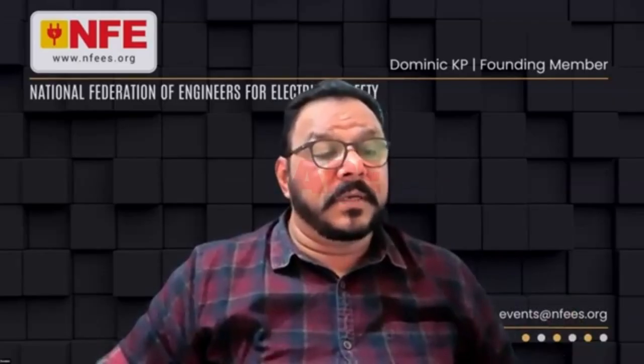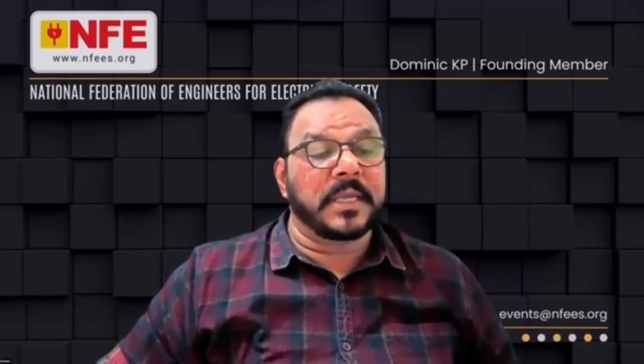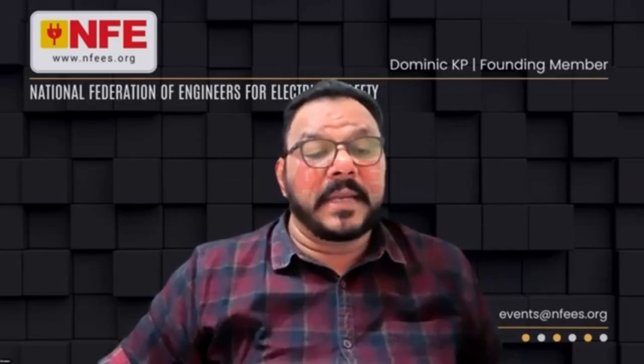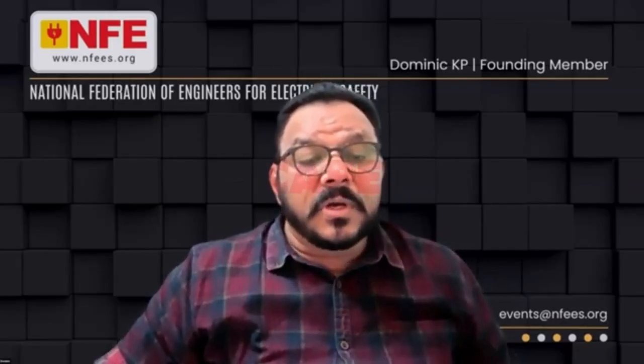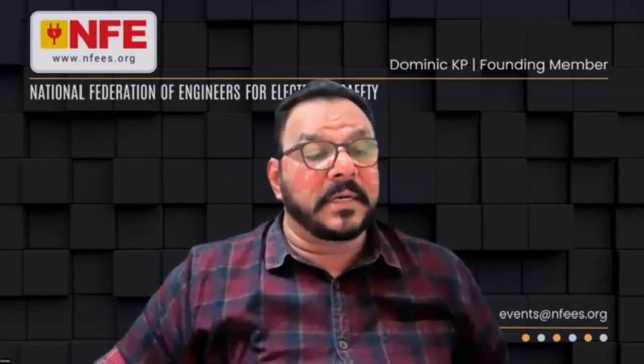Vishnu is asking, during the design stage, how can the cable length be finalized? It depends on the actual site condition. During the design stage, I would suggest going with the higher sized, higher cable length, whatever is there. You will not be able to know the exact cable length.